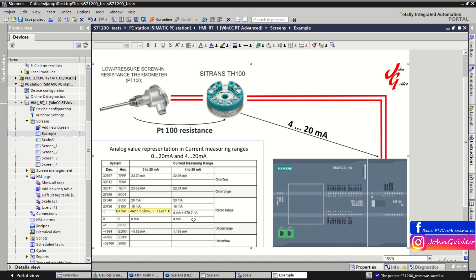This means that when the minimum input is 4mA, this is represented as 0 in our PLC program, and when it is 20mA, this is represented as 27648. There is also overrange, overflow, underrange, and underflow.